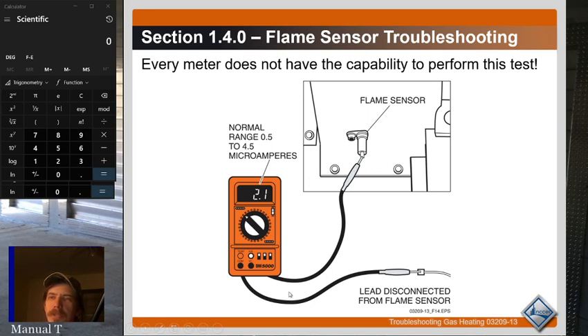You put it in series with the load, right? So one tip is going to be touching your flame sensor, then it goes through the meter, goes out of the meter, and goes to where what's supposed to be connected to the flame sensor, the lead that's supposed to be connected to the flame sensor. You disconnect that and run the signal through your meter. And you should be looking for 0.5 to 4.5 microamps, all right, which looks like a little U and then an A. That's microamps, all right. And that's definitely something you want to be in the habit of checking if you're having an issue when a flame sensor is bad.